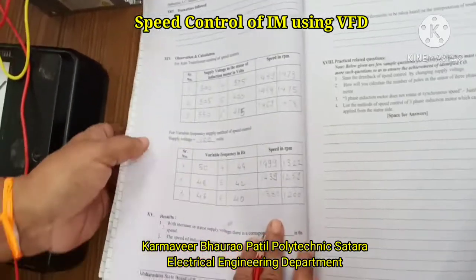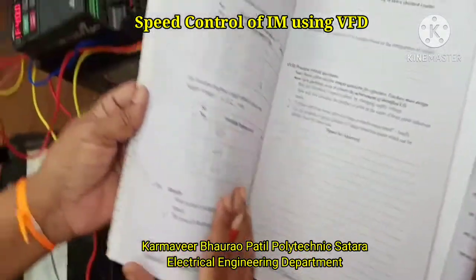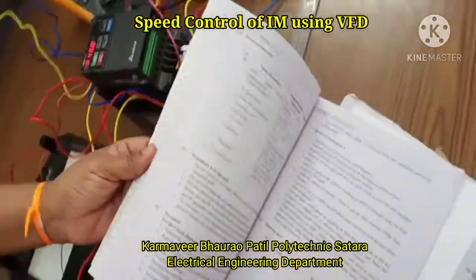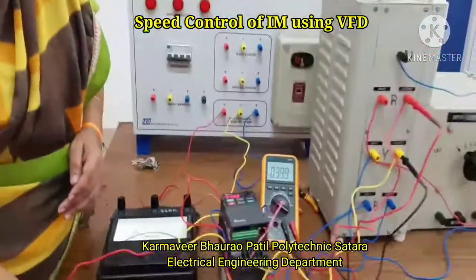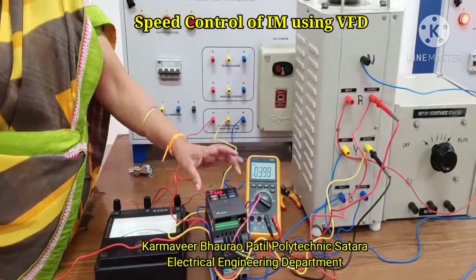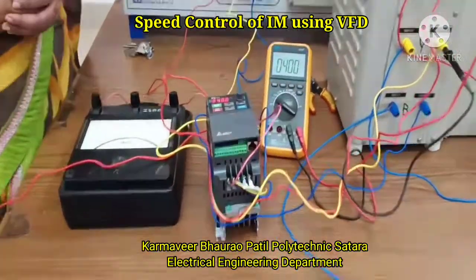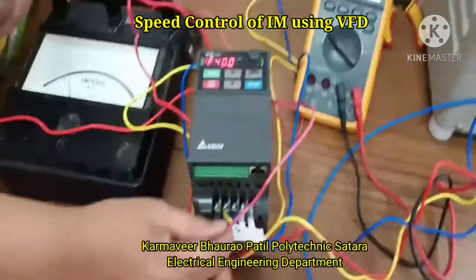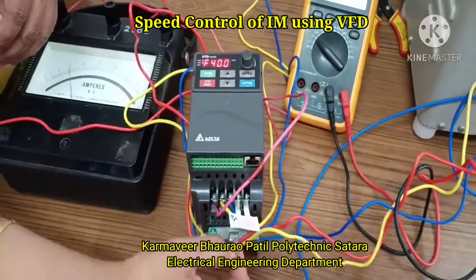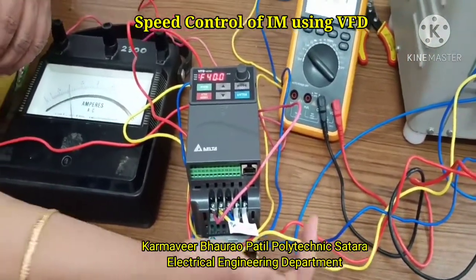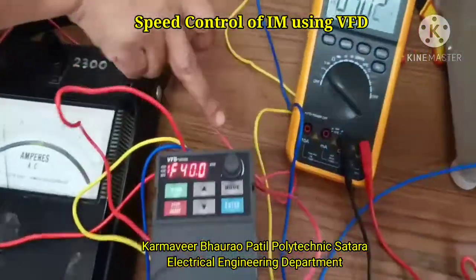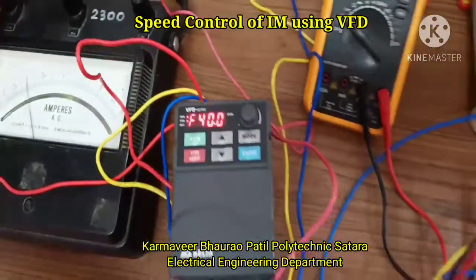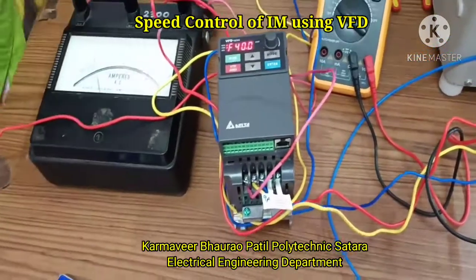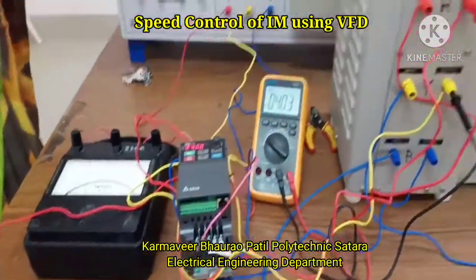Okay. So this was experiment number 6. It is actually a combination of two experiments. We have completed both experiments, and let us stop here. Once again you observe, this is a device which is known as VFD, that is a variable frequency drive. I have made that connection which was loose. These are the 4 input terminals. Once again I write on this side R, Y, B and N, and here on the output side R, Y, B. So a simple block with 3 input terminals, 3 output terminals, and one particular wire which is to be connected to the earth.